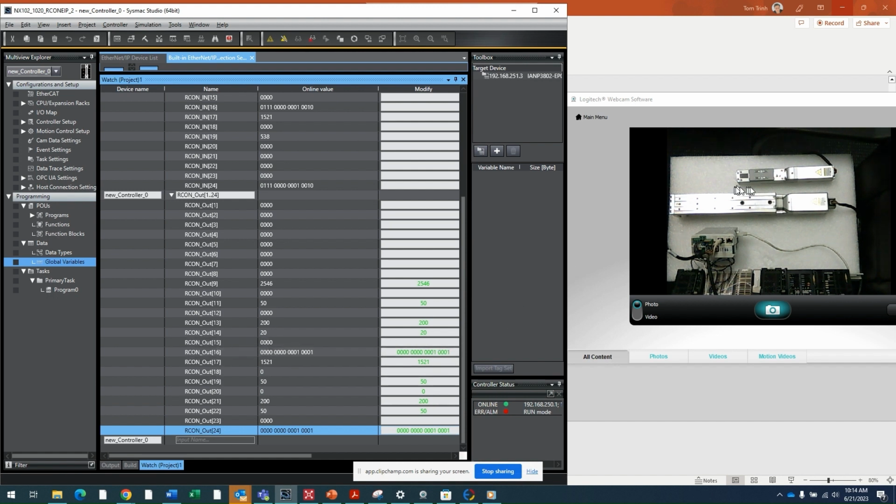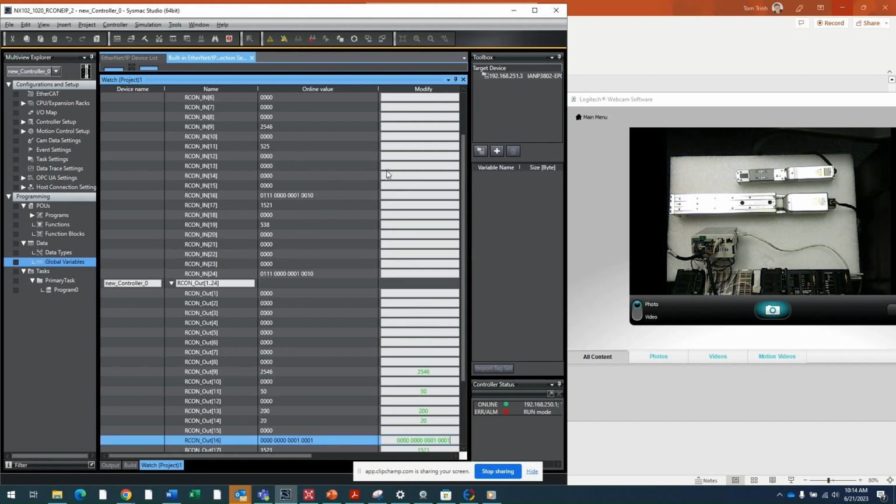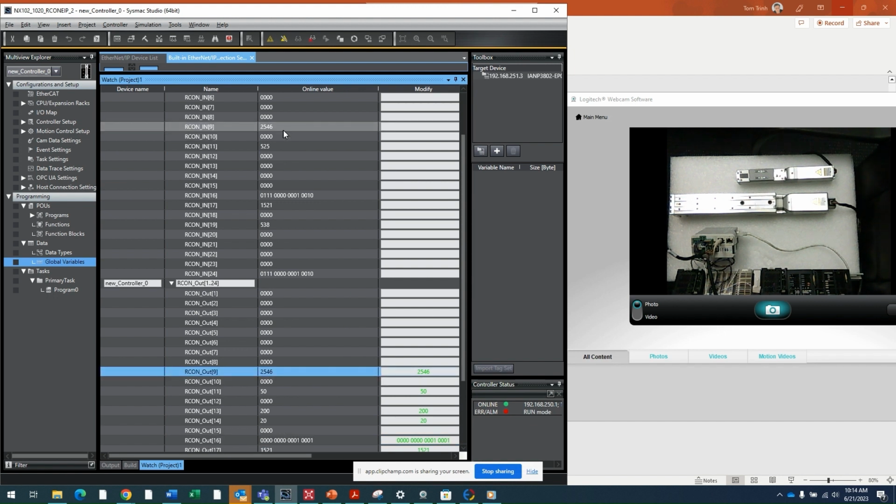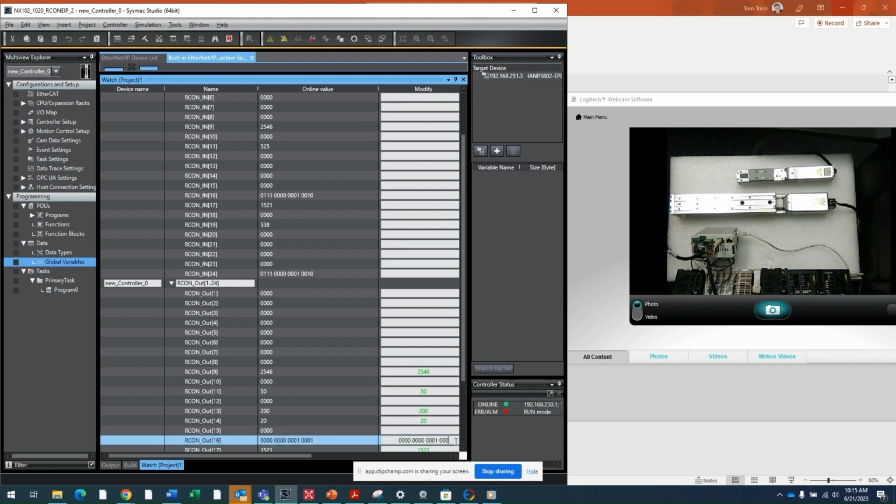All right, let's go to this actuator real quick. So right now, that actuator is at 25.46, as I commanded it to go there before. I'm going to have it go home, okay? To do that, I'm going to flip the bit here, which is this bit right here. As soon as I do that, the actuator will roll and it will update. This should be 0. Here we go. It's home, and it is also at 0. Beautiful.